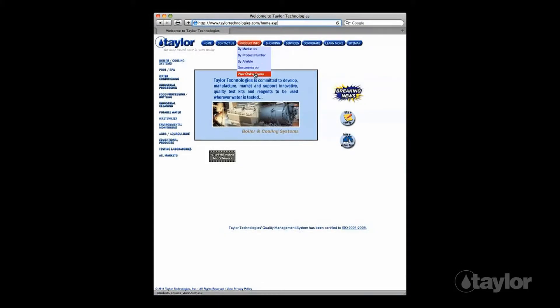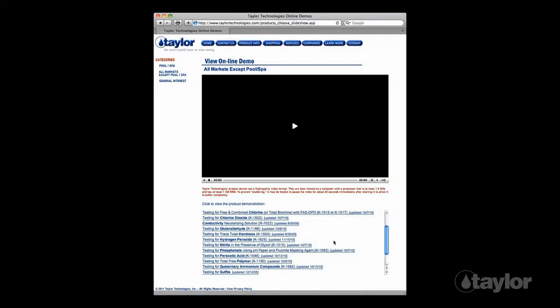Taylor's test kits for nitrite incorporate either the permanganate or the CAN (ceric oxidation of nitrite) method. The CAN test is perennially a bestseller, but when raw materials for the CAN titrant become difficult to source and pricing increases, the permanganate method offers a cost-conscious alternative — if the system has not been treated with glycol. A video illustrating the CAN method, titled 'Testing for Nitrite in the Presence of Glycol,' can be found in our online demo library.